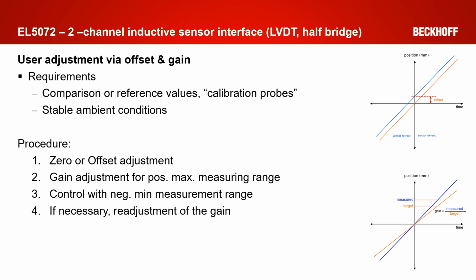In the next step, you can travel to the maximum positive measurement range and also check the output values here. Now you can implement the gain, so you will just set the ratio of the measurement and the target value, and put this into the gain register. Then you can do a cross-check by traveling to the maximum negative measurement range. Probably you will need to do some readjustment to achieve a symmetrical behavior.